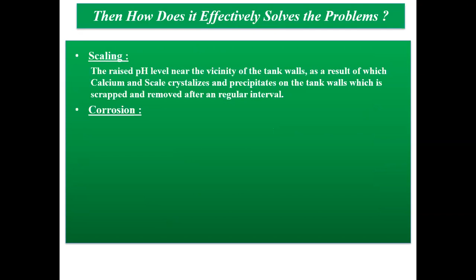How does this solve the problems effectively? Since the pH near the tank wall is highly alkaline at 13, and we know calcium tends to precipitate where conditions are warm and pH is high, the cooling tower zone provides the warmth and the tank provides the high pH. This makes the tank itself prone to calcium settling, rather than it settling anywhere in the condenser loop.